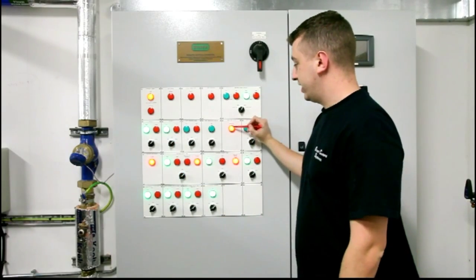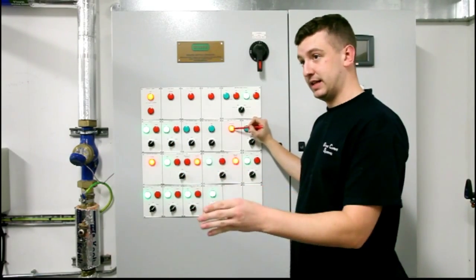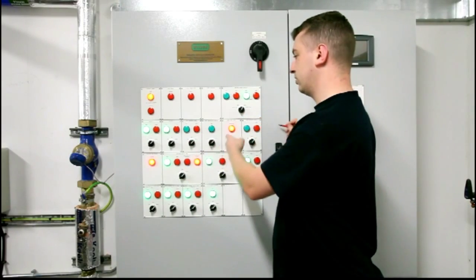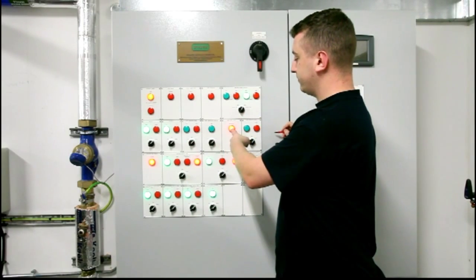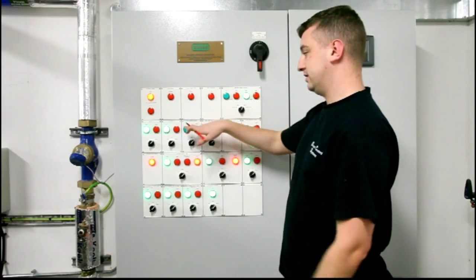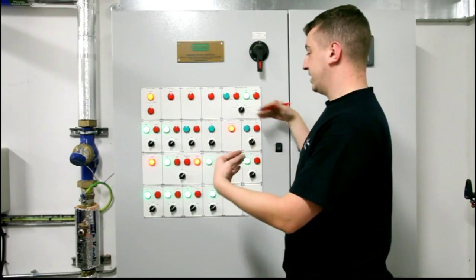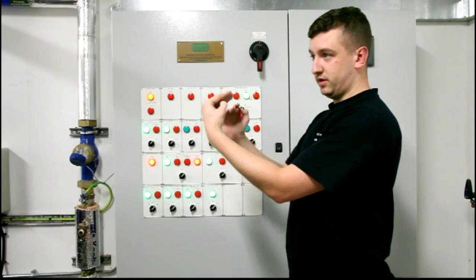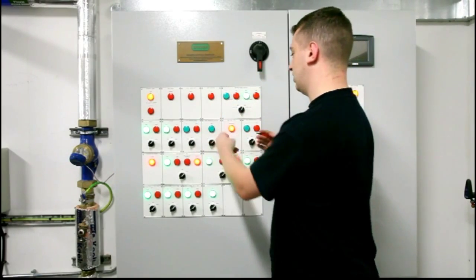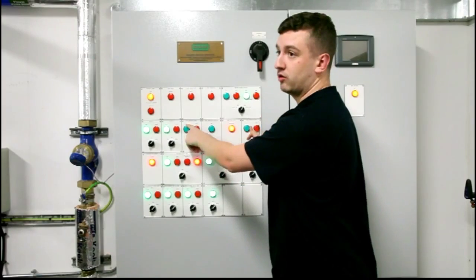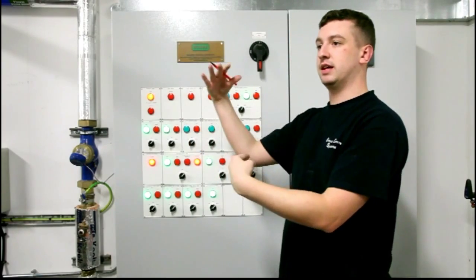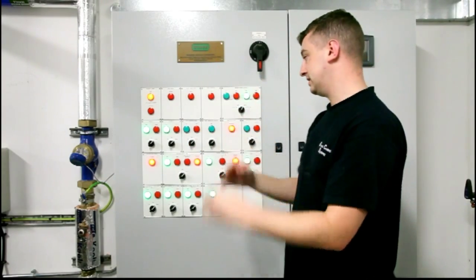basically it's run via a high limit stat in the cylinder, which I think is what we just ran through. When the high limit stat makes, it turns off the pump and the return pump until it drops below its 55 degrees again, at which time that goes off, the pumps start running again, and it tops it up to 60, and it holds that cylinder at 60 degrees.